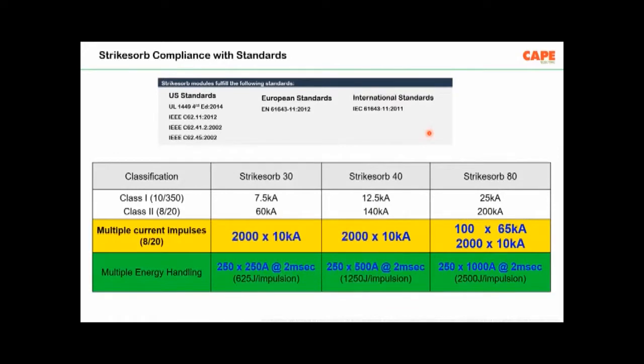Similarly, we should also understand that lightning, which is also an EMP, is not a one-time phenomenon. Lightning probably comes very frequently. Maybe within 5 seconds or within 5 minutes of one strike itself, you will have multiple strikes. If we look at the conventional DIN rail mounted SPDs, these SPDs are tested for one pulse. Then the SPD heats up, the temperature is brought down to room temperature, and then the next pulse is given. That means in the testing, between the pulses, there is a certain cooling down time. This is allowed in the standard, but the lightning will not wait until your SPD cools down. It may come quite frequently.